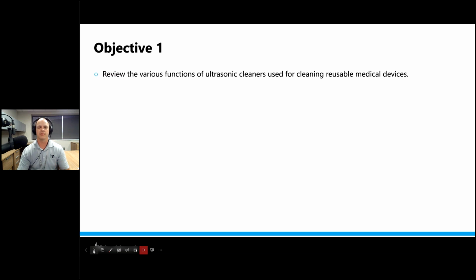All right, so basic function number 2. The other thing that is really important about ultrasonic cleaners is that it actually removes surgical soils. This is common. So these functions, function number 1 and function number 2, are common with all ultrasonic cleaners, and that goes for any medical device ultrasonic cleaners in sterile processing, or in the automotive industry, they clean auto parts with ultrasonic cleaners, or in jewelry, they clean jewelry with ultrasonic cleaners. It's got to remove soil and it's got to produce cavitation, and both of those things kind of go hand in hand. All right.